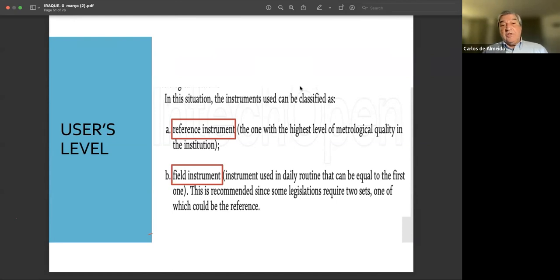And then when you have to send one of the two for calibration to the secondary standard lab or to a primary standard lab, you can use your reference instrument and keep the field instrument in the institution. And when the instrument comes back, you can perform a cross calibration to make sure that the field instrument is working with the same qualities as before. Next one.